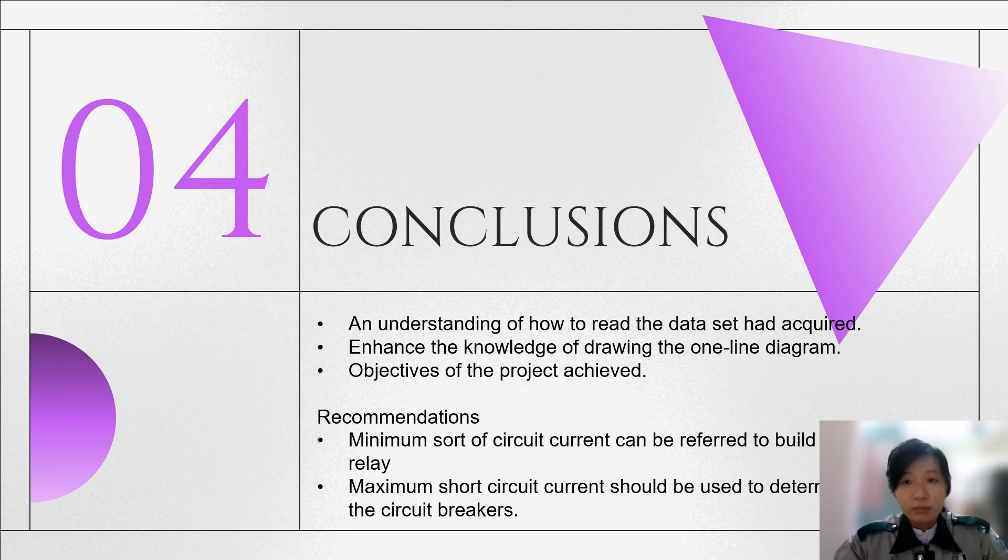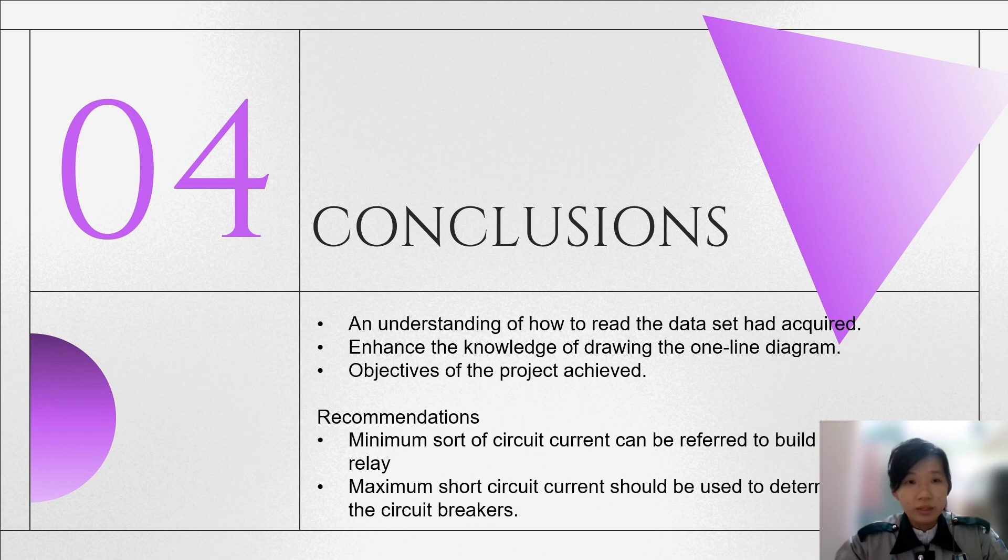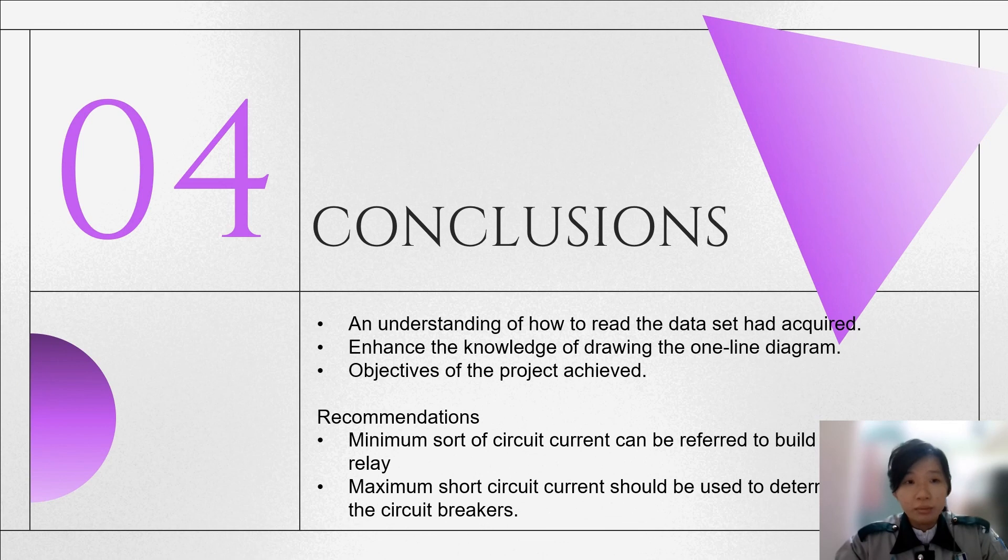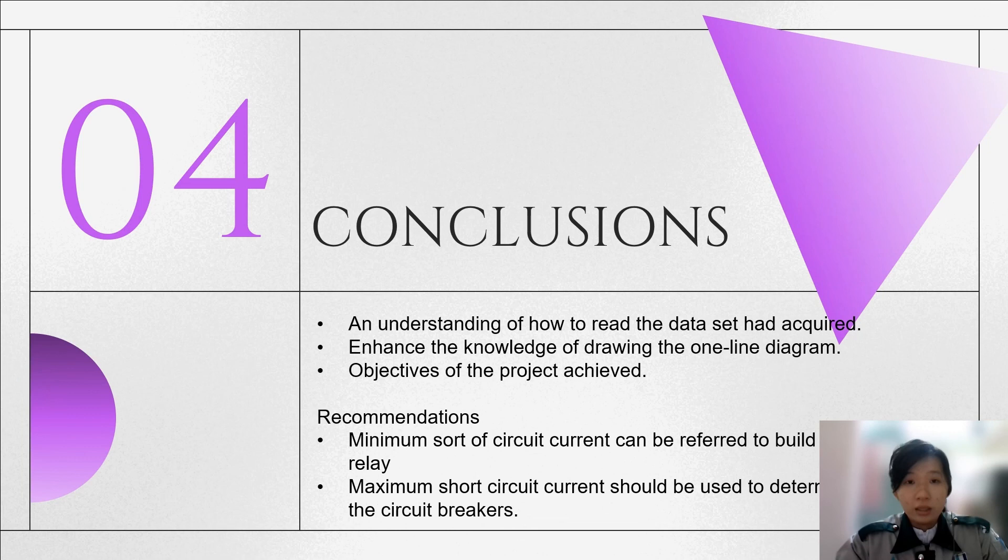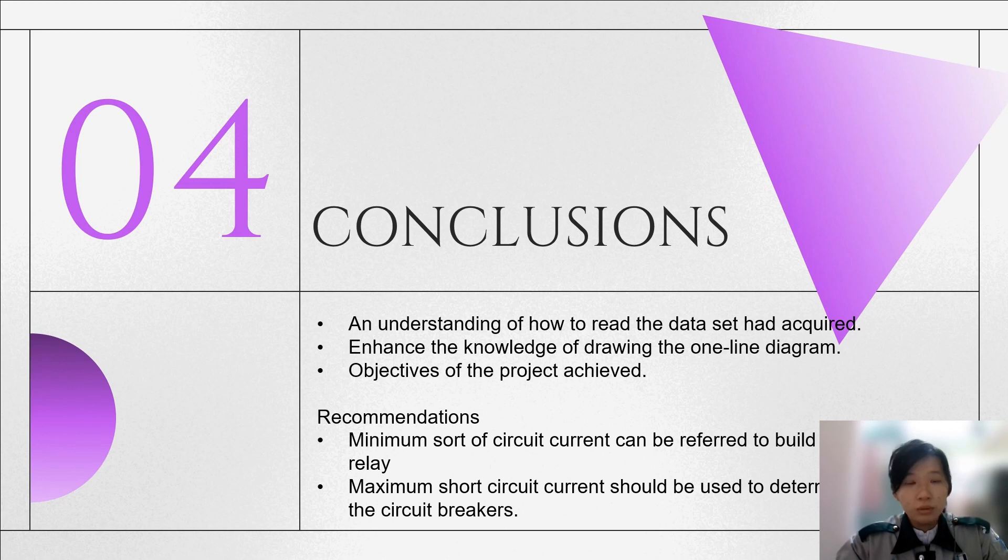Lastly, there are some recommendations on the IEEE 14 bus system: the value of the minimum short circuit current can be referred for the protection relay, while the maximum short circuit current should be used to determine the rating of the circuit breakers. This can improve the safety and protection of the bus system.